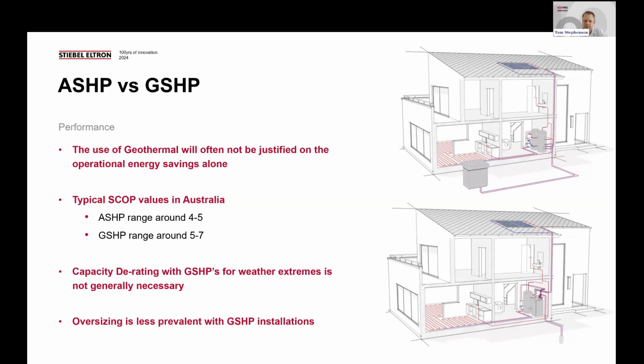Also, we see that, particularly in various comparisons, that air source values and probably even ground source performance values are generally underrepresented or underrated. We have a very strong resource in our ground temperatures in Australia, and certainly access to water bodies, as Yale's mentioned, which sees us achieve much higher values in actual performance than stated on brochures or as represented by EN test values. So normally we'd be guiding our clients on an air source heat pump performance range of somewhere between a COP of 4 to 5, with a ground source comparison of 5 to 7. So realistically, the ground source is probably performing much better than that in certain applications. But as Yale pointed out, every site is conditional.